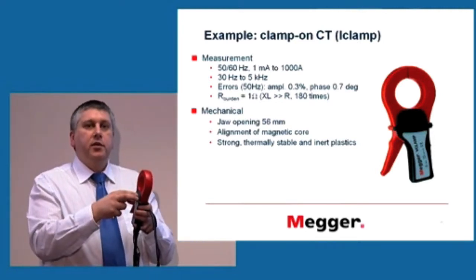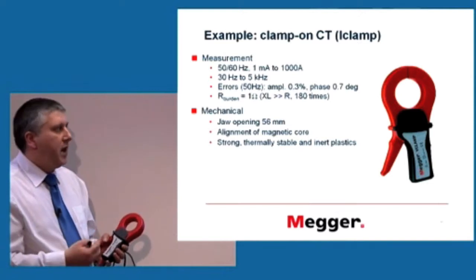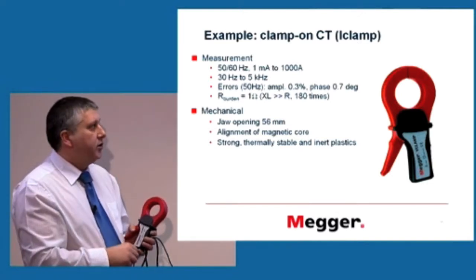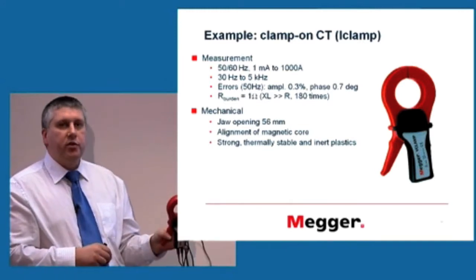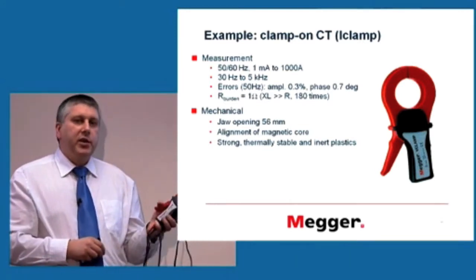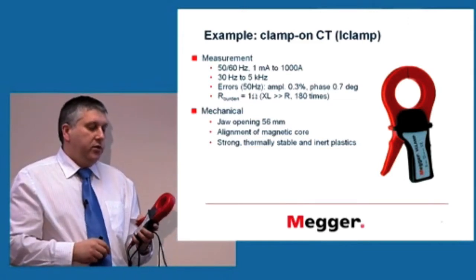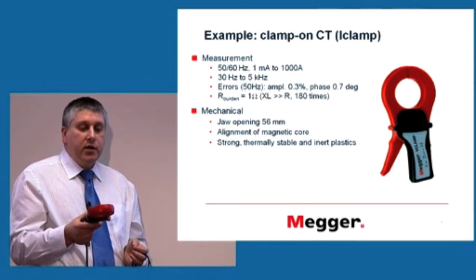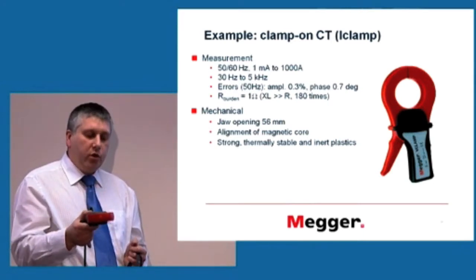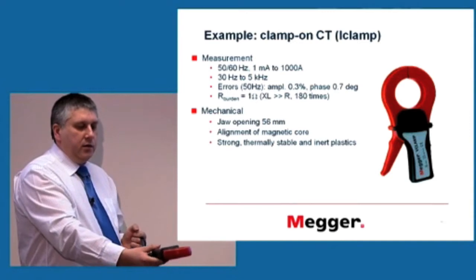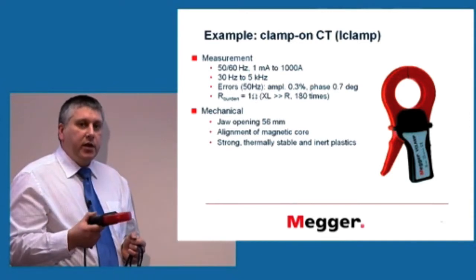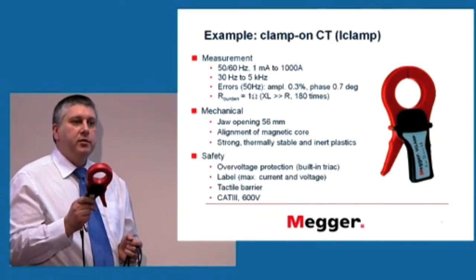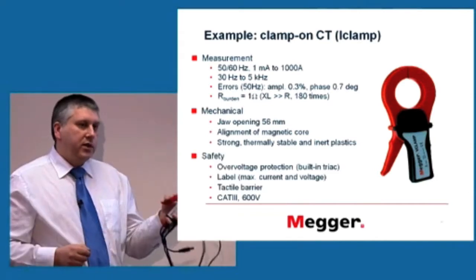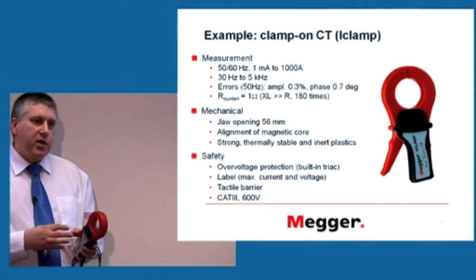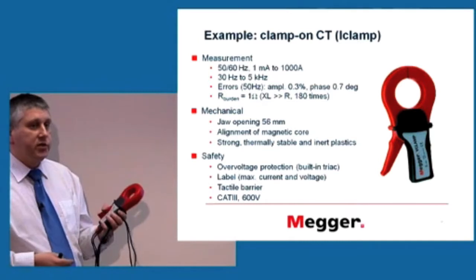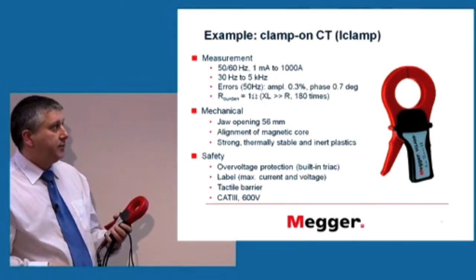If it was slightly shifted, we would lose some of the cross section, and that would impact especially on the high current range. And of course, the plastics have to be strong. They cannot be affected by temperature to whatever limit is defined. The safety standards, for example, state that devices like this have to survive a drop onto concrete from 1 meter. And the device can be affected by this on any level, but not safety. It still has to be safe to clamp around something. It doesn't have to work, it doesn't have to be accurate, but it mustn't be unsafe, which obviously puts quite a strong requirement on the plastics.